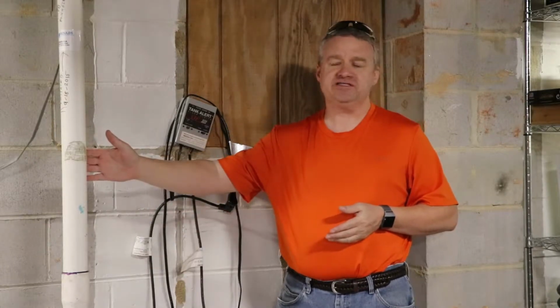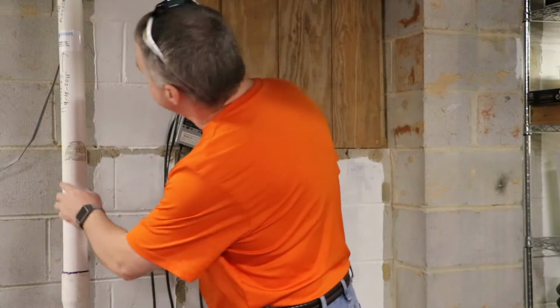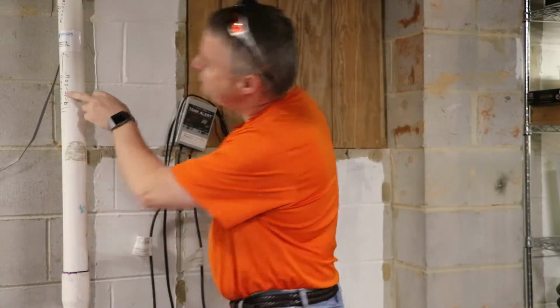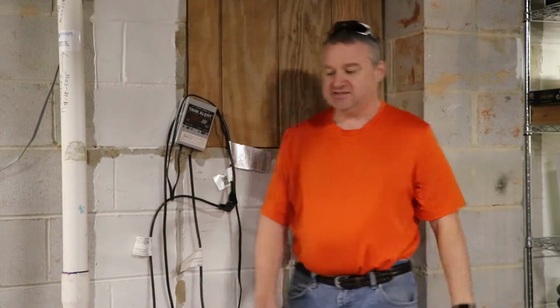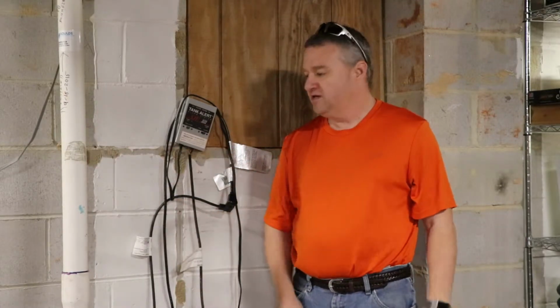It's been on my radar because it's gone bad once, and I knew it was probably going to go bad again, just because they do go bad. I believe this was replaced, give or take, somewhere around 2015. In fact, there was actually a label on here, 2015. So it is now 4 years old, and it has gone bad again. It's locked up. Basically, I walked down here after the alarm went off, and it was just sitting there making a noise, locked up.